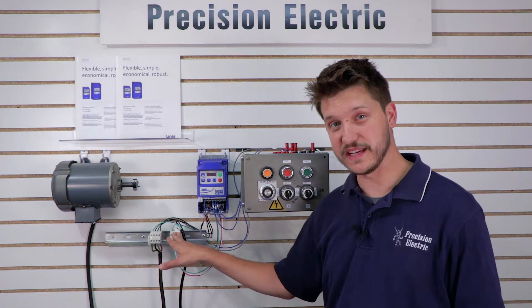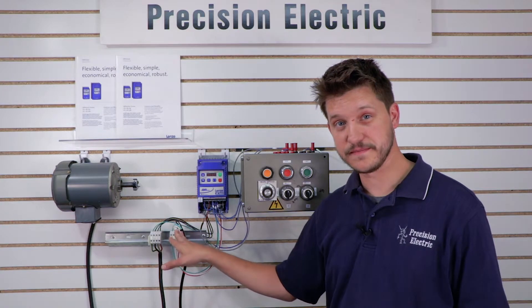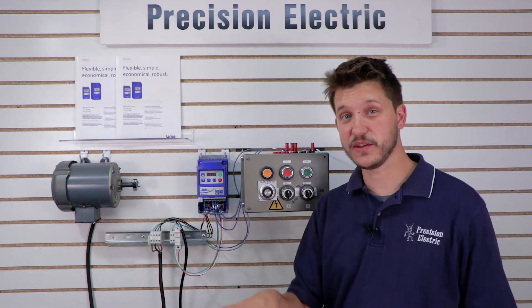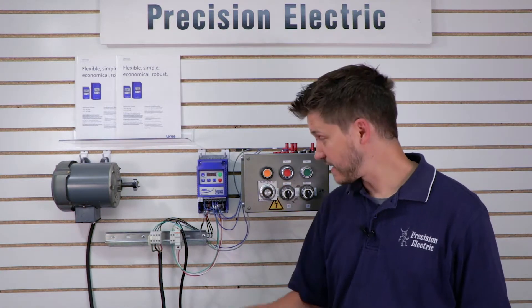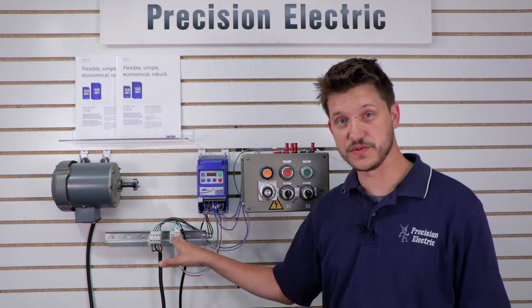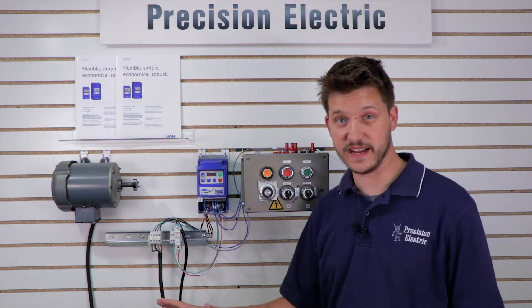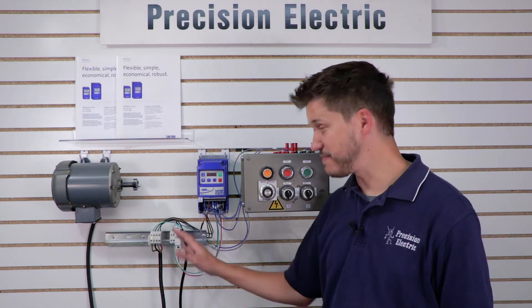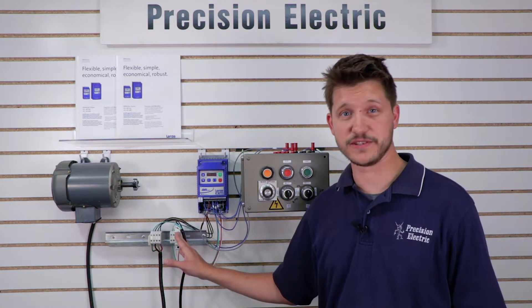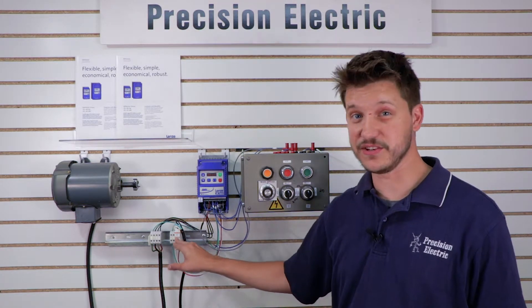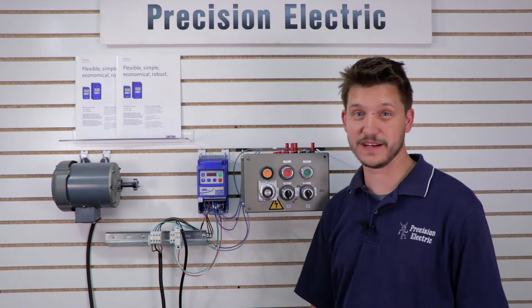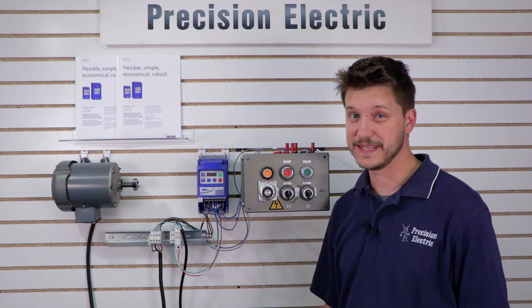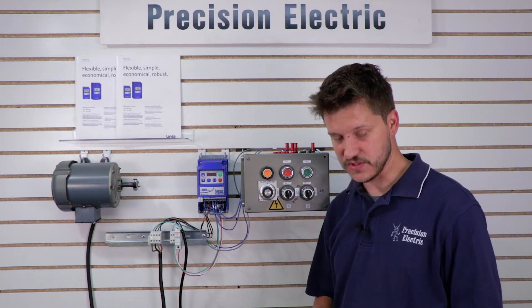And that will properly protect the input power on your drive. That's really all there is to it. Just make sure you fuse it, you size the fuses properly, you buy the right fuses, current limiting fuses, and you wire all the hot wires to those fuses. Your drive's protected. I'm not saying that in a hundred percent of instances you'll always be protected, but you've maximized your potential for protection. If it blows up after that then you just got really bad luck. You can get a power surge that blows the drive up before the fuse blows, but it'd have to happen really quick at that point.